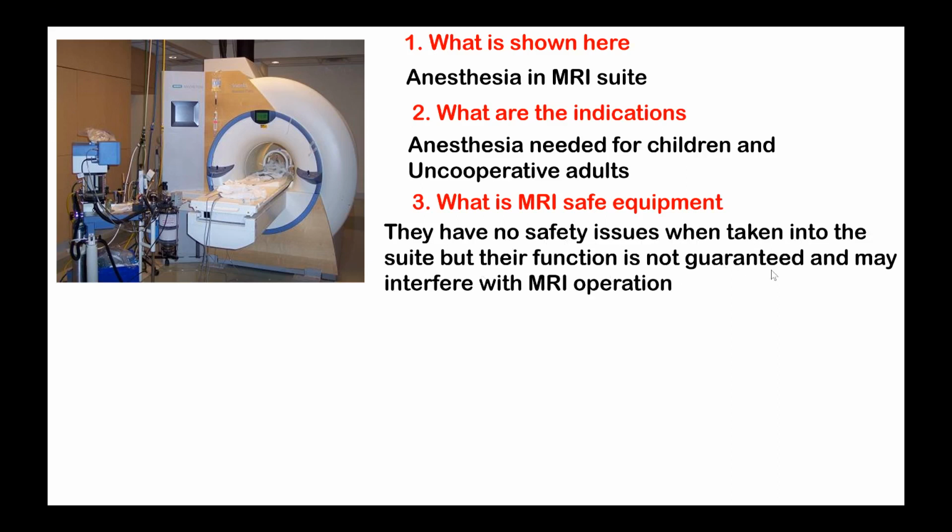Their function is not guaranteed. It may interfere with the MRI operation itself. So they will not be attracted by the magnetic field like a metal, a dental prosthesis, or a metal clip in your joints. All these things will not be attracted if it is MRI safe equipment. There is assurance that it will not be snatched away by the magnetic field, but it will not guarantee the functioning of that particular equipment, or it may interfere with the operation of the MRI itself. That is called MRI safe equipment.